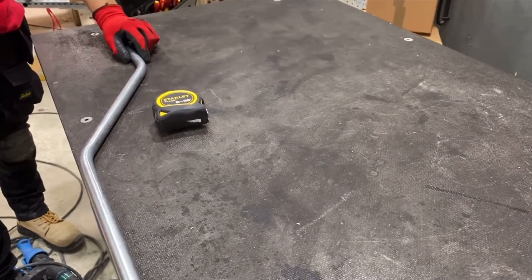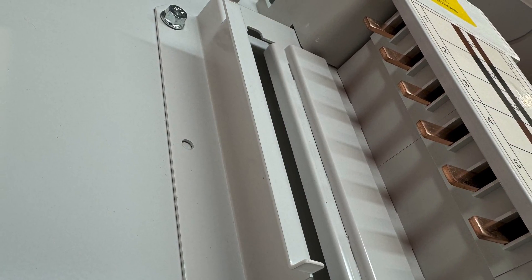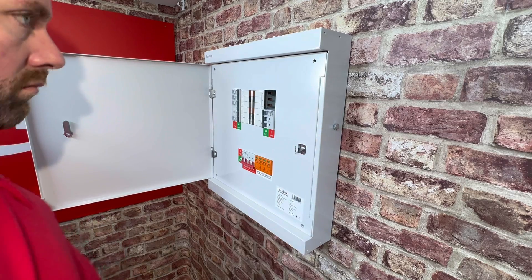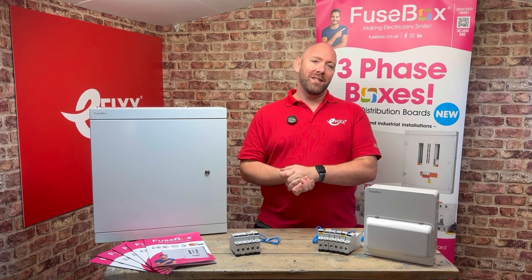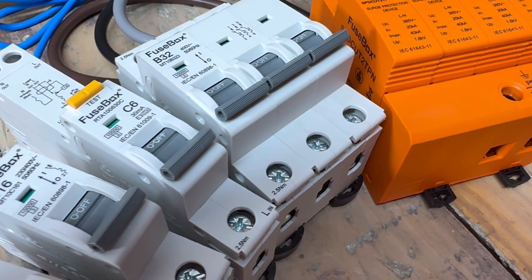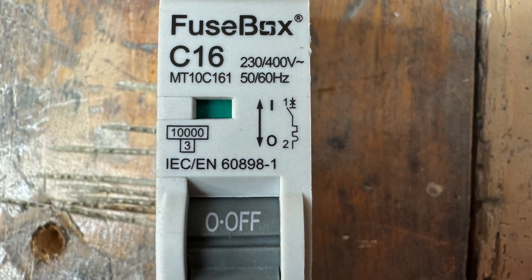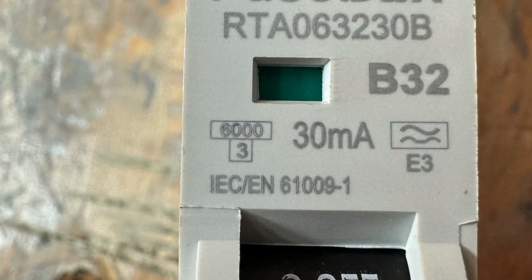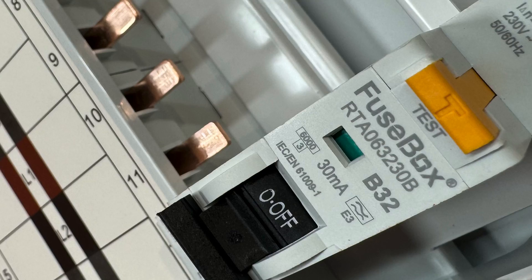Let us know what you think in the comments below. Here's another thoughtful touch which I wish all distribution boards had — you have these pan end stops which keep your protective devices in line. That might not seem interesting now, but when we come to put the lid back on it keeps all your devices in line so you don't get snagged behind the lid. Your standard Fusebox protective devices including MCBs, RCBOs, AFDDs, and SPDs all fit in the board. Fusebox have added to their range with 10kA short circuit capacity available in type B and C. Even better, Fusebox's 6kA devices will fit into the board, so no hardware change is required between the consumer unit range and distribution board range.